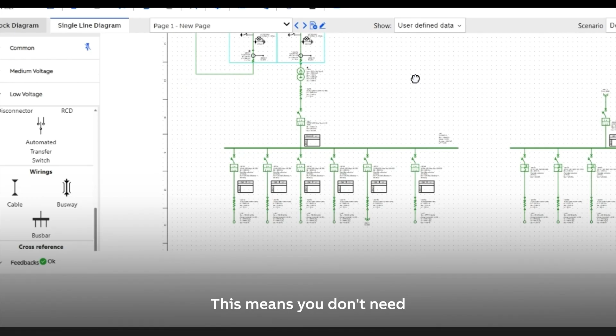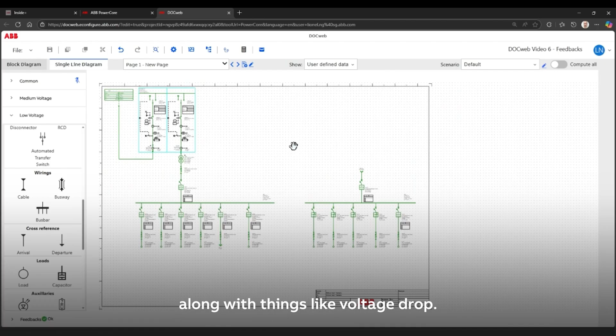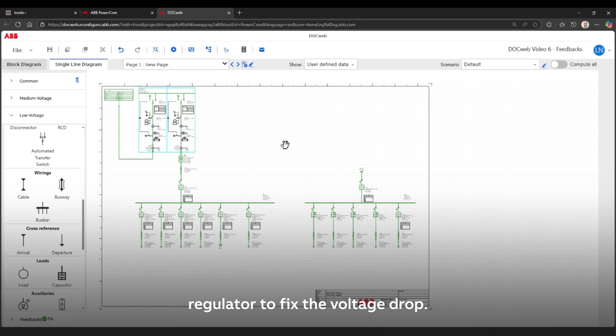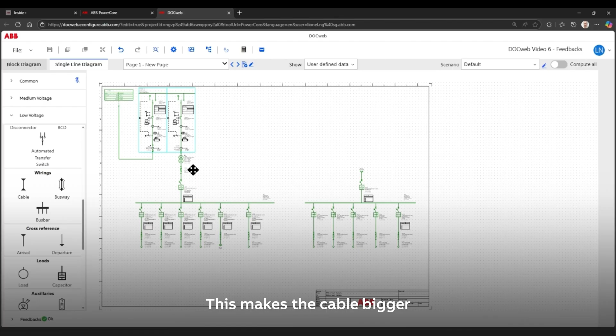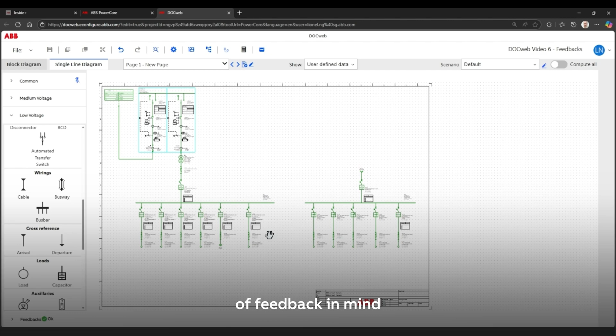There are a couple of ways to solve this kind of feedback. It's important to understand what these feedback messages mean and how to solve them. These 2 or 3 feedbacks are common, along with things like voltage drop. As I mentioned earlier, you can use the transformer regulator to fix the voltage drop. Another way is to increase the size of the cable. This makes the cable bigger and helps remove voltage drop, so keep these types of feedback in mind and how you can solve them.